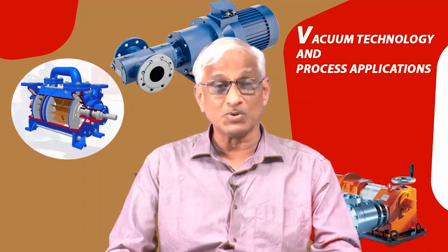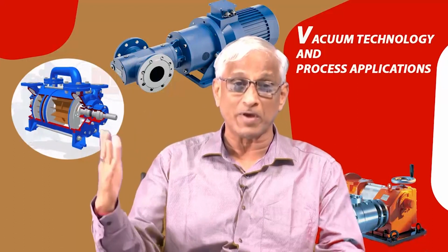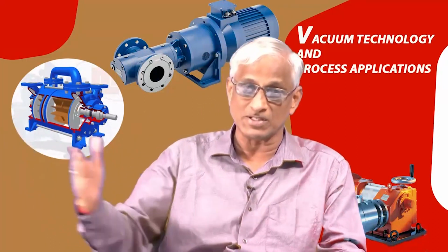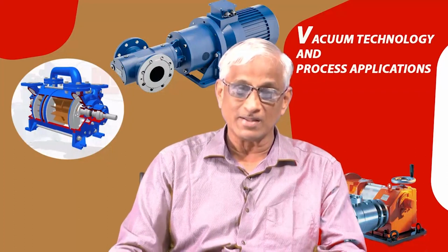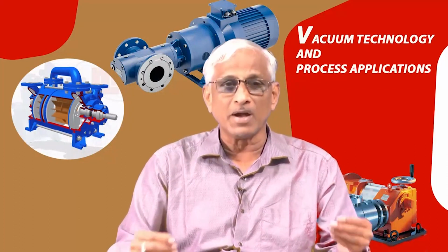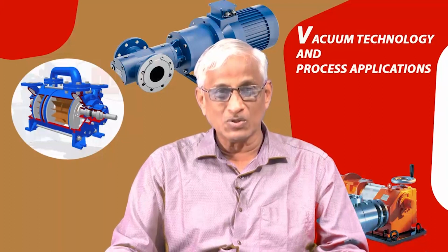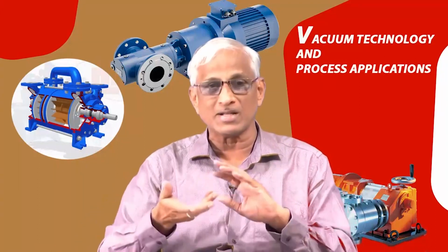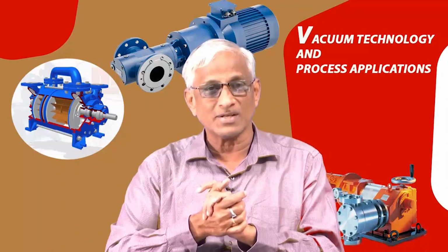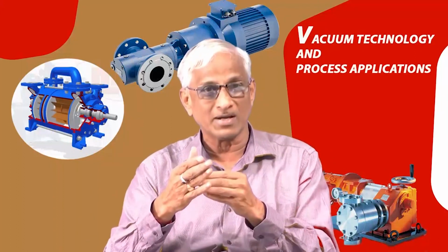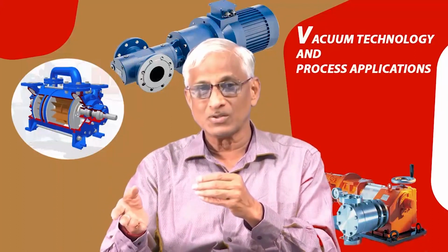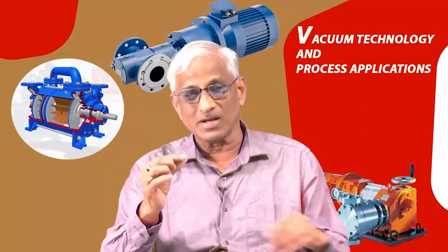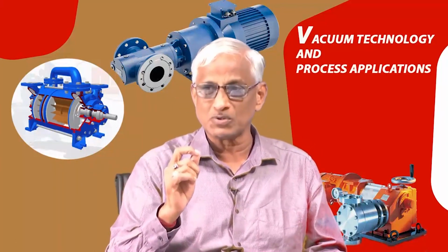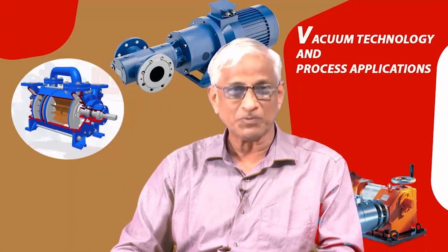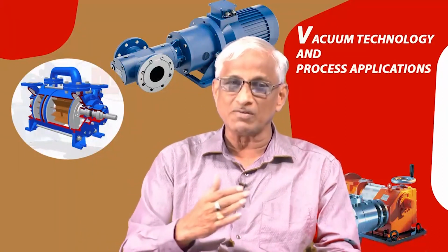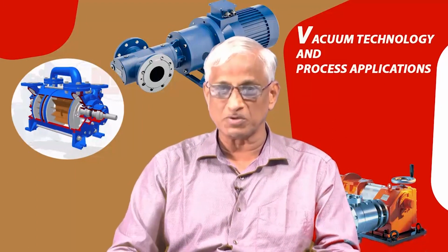Earlier it was not possible to make these things, because in poor vacuum, that is at slightly higher pressures from 760 torr to 10 torr, etc., the mean free path is still about 0.01 millimeter. Whereas, in dry pumps we need to maintain clearances between the housing and the rotors. So, that housing will look big compared to the mean free path. So, unless you reduce the clearances to very small values, which are possible with advanced machining, you cannot operate them at relatively poor vacuums or low and medium vacuums.